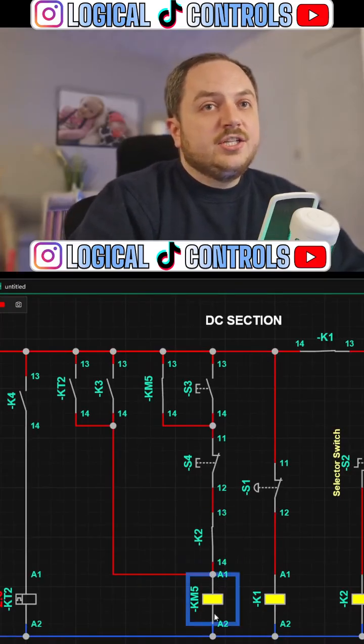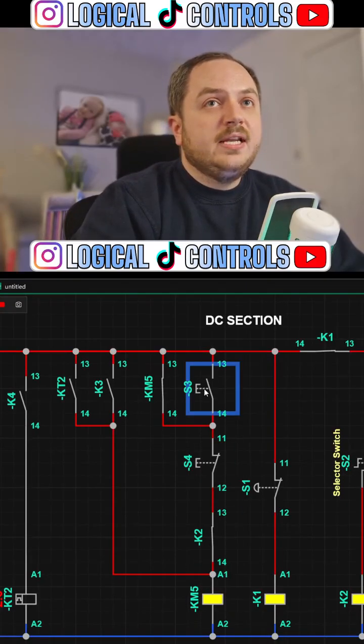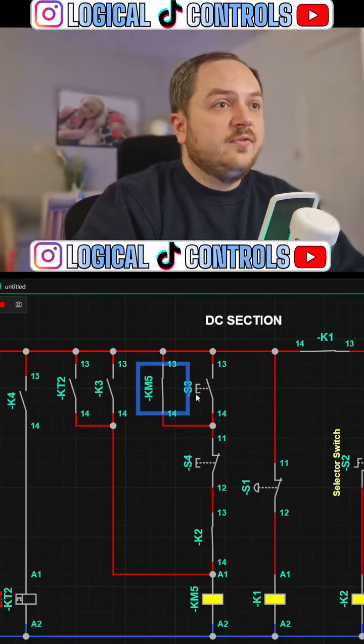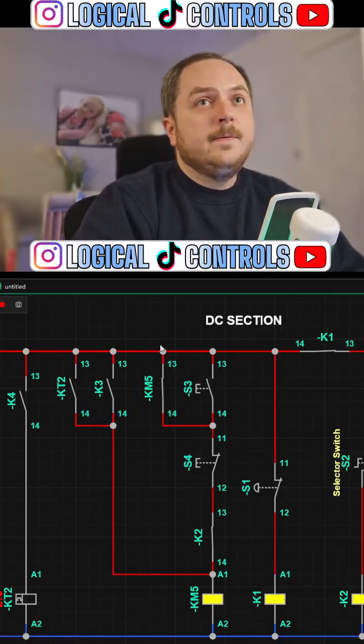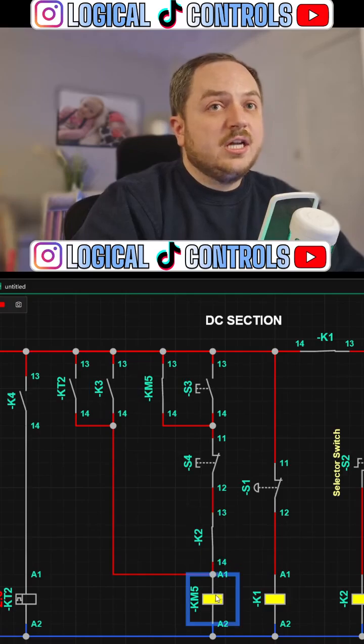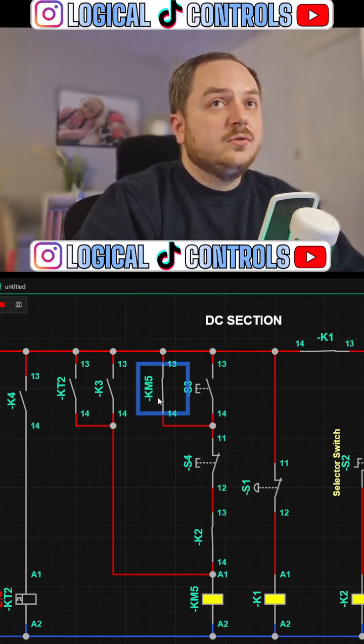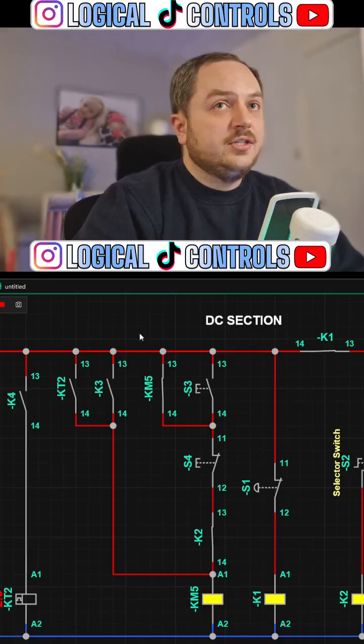And then that's energizing KM5. The minute we let go of that button, if we didn't have a latch in here, KM5 would de-energize again. So what I've done is I've put KM5 in parallel to the start button. The minute I press the start button, KM5 energizes and latches itself in. So this contact here, whenever that's energized, holds in.